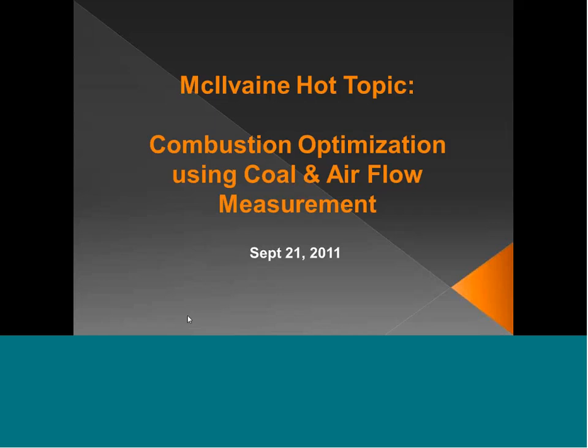I guess I'll point out also that this has been used, the coal flow measurement, for instance, on every fuel type, every milling type: ball mills, ball tube mills, exhauster mills, pressurized mills. There's not one out there that we haven't installed this equipment on. It is not new anymore. We have well over 100 full boilers that we've installed all this equipment on.